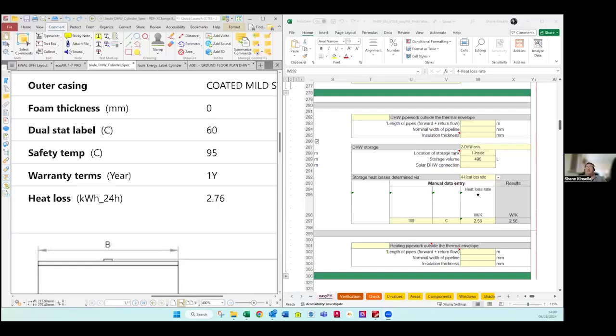That's a good question. I'm not particularly familiar with the Pichler PKOM4. I have come across it on my travels, but not to a great degree. But if it has cooling test points and that kind of information available, then absolutely we can enter it into the components tab and assign it as a cooling approach for our dwelling. So I don't see any problem with that. If the unit is only providing a small bit of cooling, just for tempering, you wouldn't include that in PHPP. But if it's actually providing full supply air cooling, then yes, you could enter it into the components tab. That's great. Thank you very much, Shane.